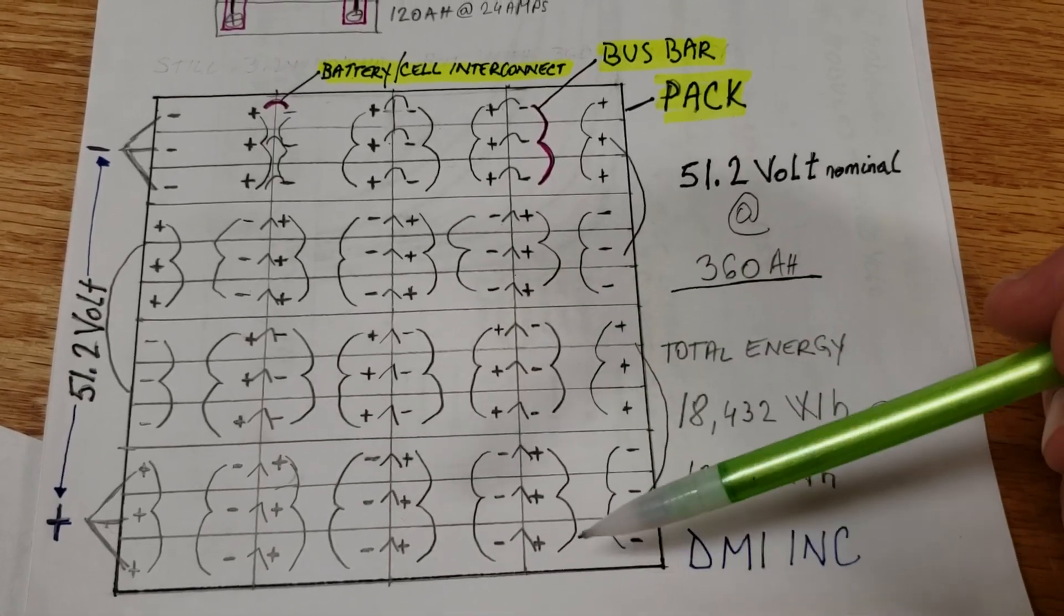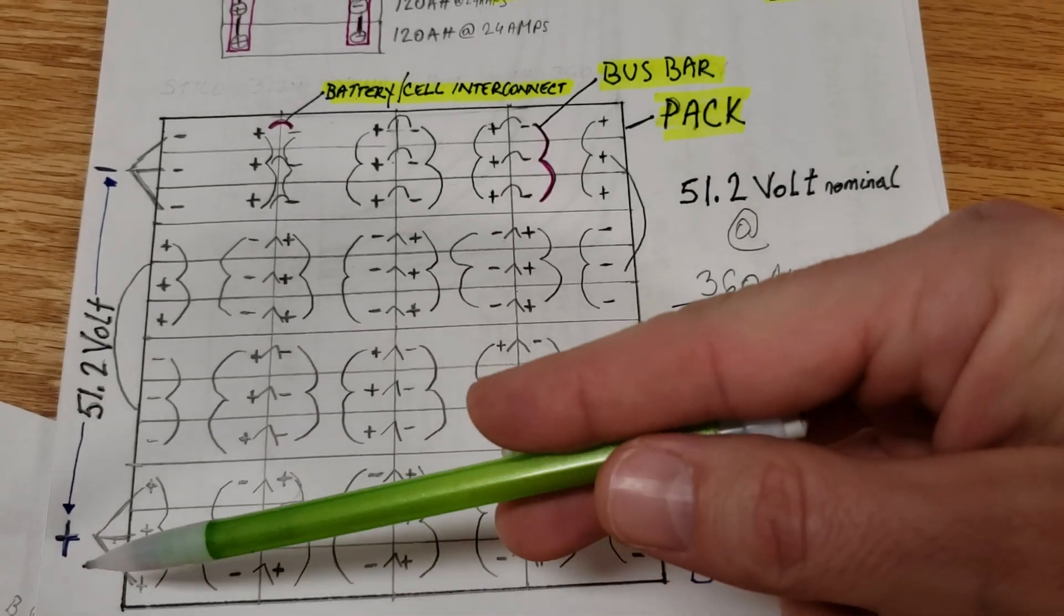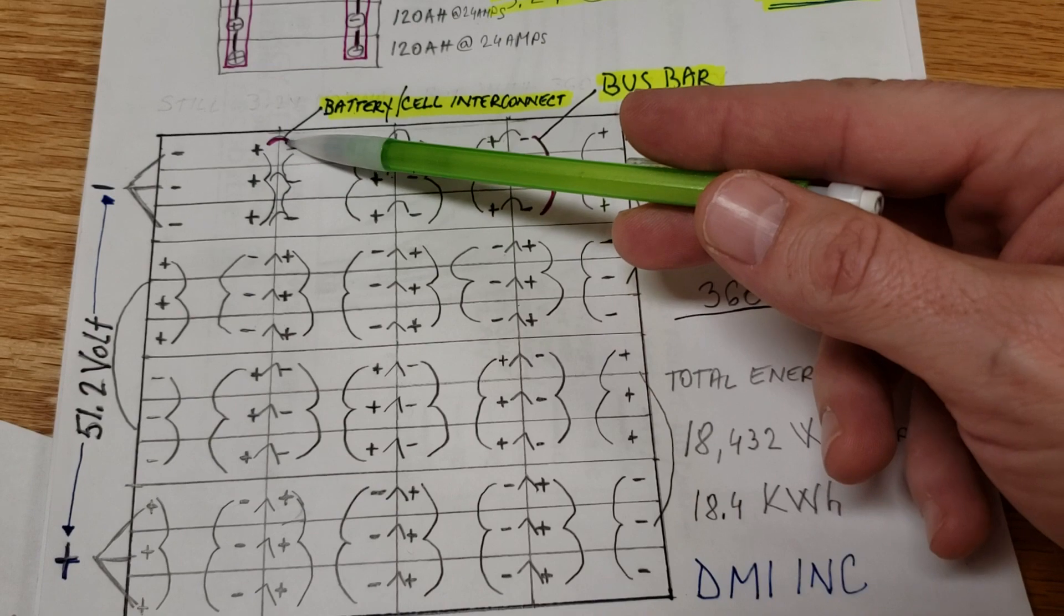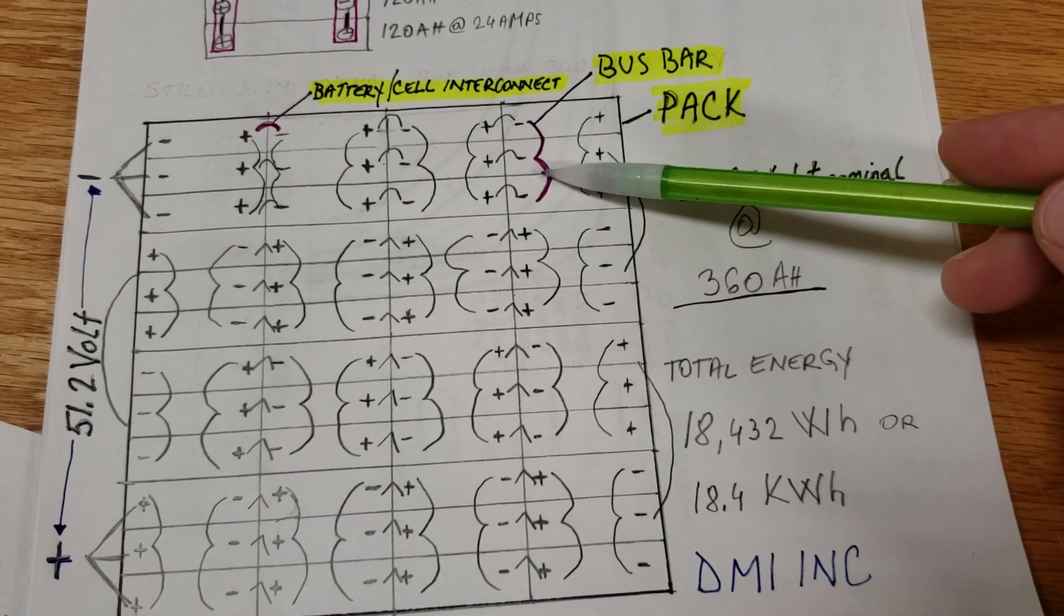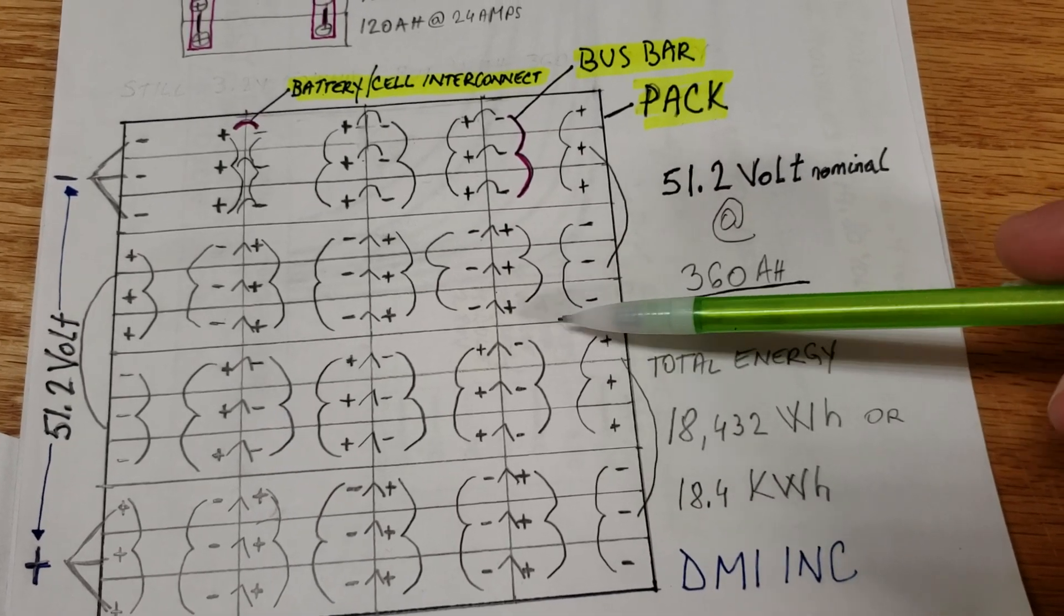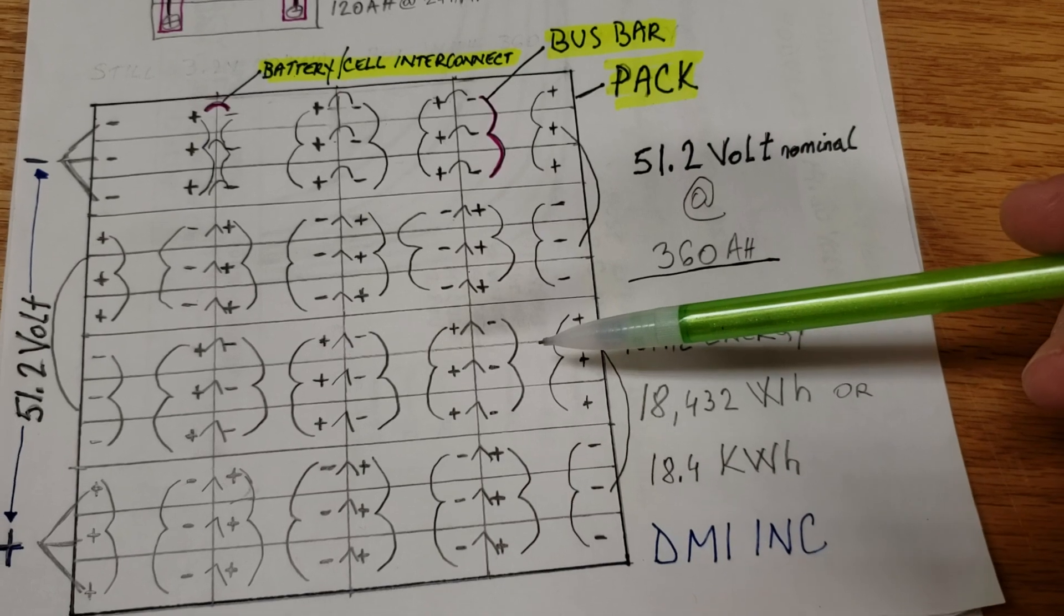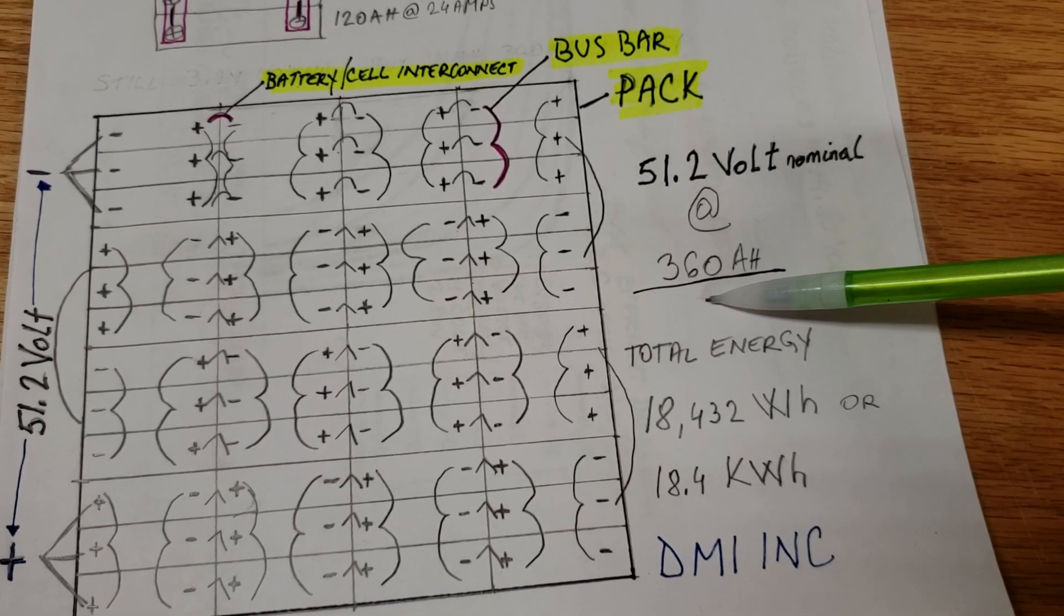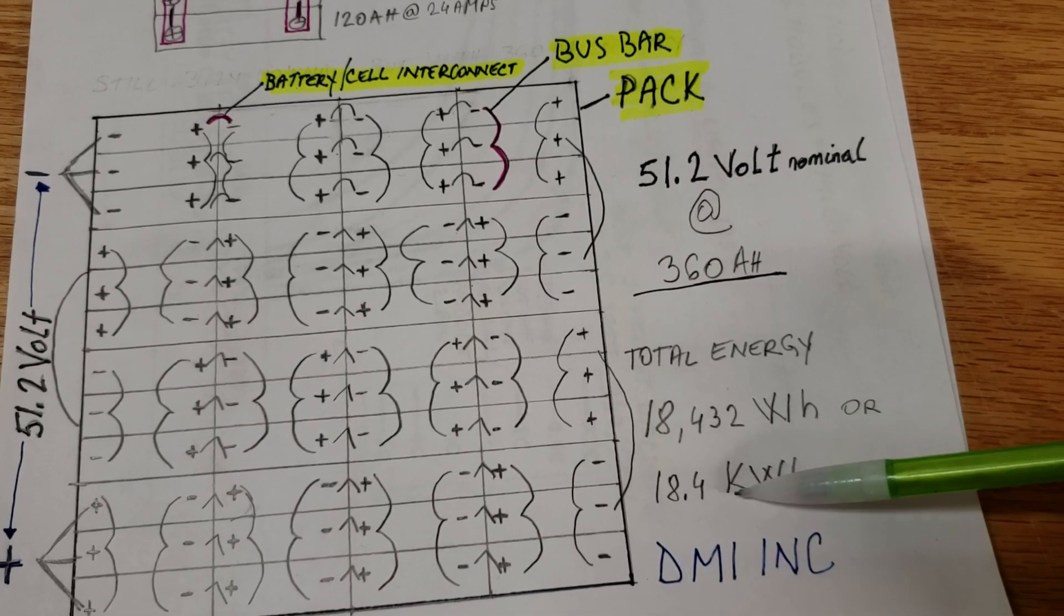Now we see on the paper representation of my total power pack or power wall or battery pack. Over here on bottom left we have the positive and they interconnect with each other. Each of these lines represents that battery cell interconnect cable, and each one of these lines indicates a bus bar. When you add all of these modules at their nominal voltage of 3.2 volts, and there are 16 of these modules, you will get total voltage of 51.2 volts nominal at 360 amp hours. Total energy is 18,432 watt hours or 18.4 kilowatt hours.